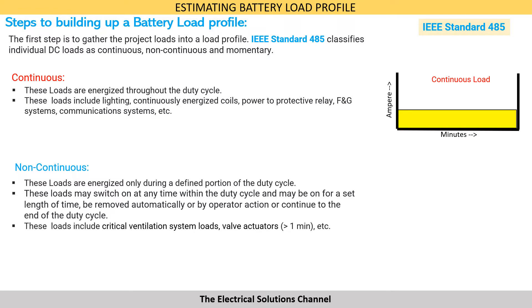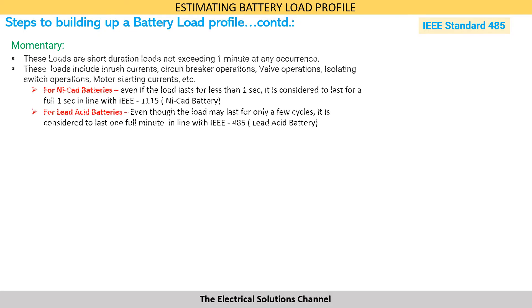Non-continuous loads are those which are energized only during a defined portion of the duty cycle. These loads may switch on anytime within the duty cycle, may be on for a set length of time, and can be removed automatically, by operator action, or continue to the end of the duty cycle. Examples include critical ventilation system loads and valve actuators. Momentary loads are short duration loads not exceeding one minute at any occurrence, such as inrush currents, circuit breaker operations, and valve operations.